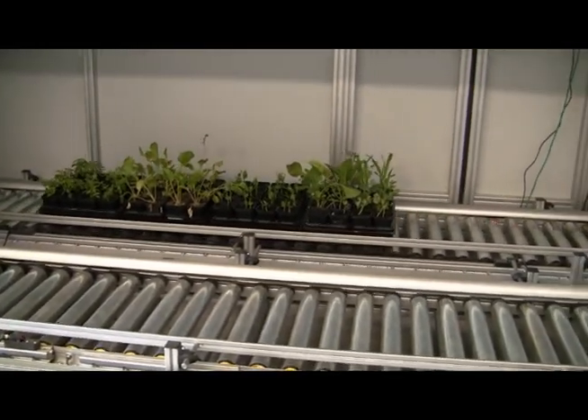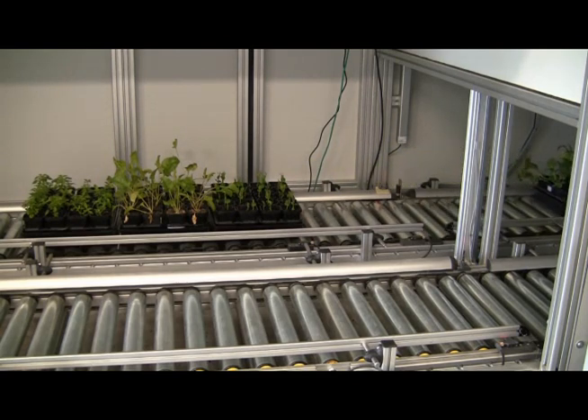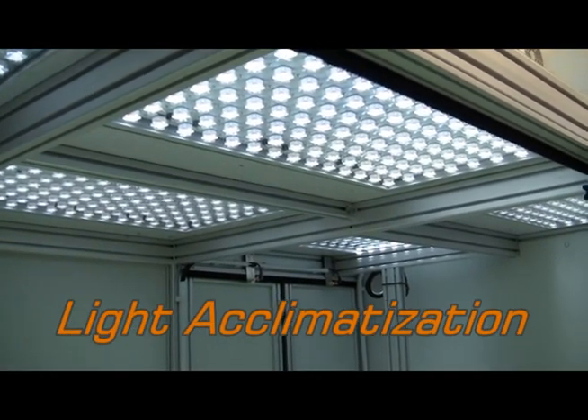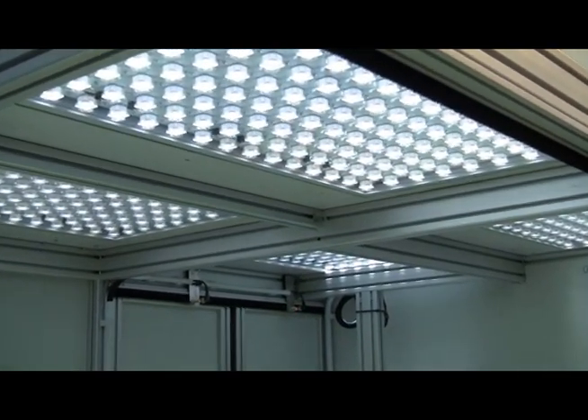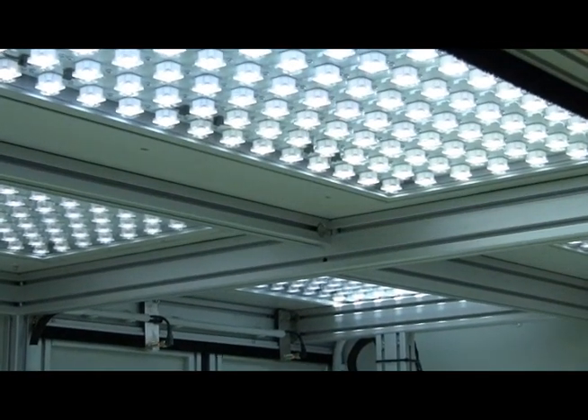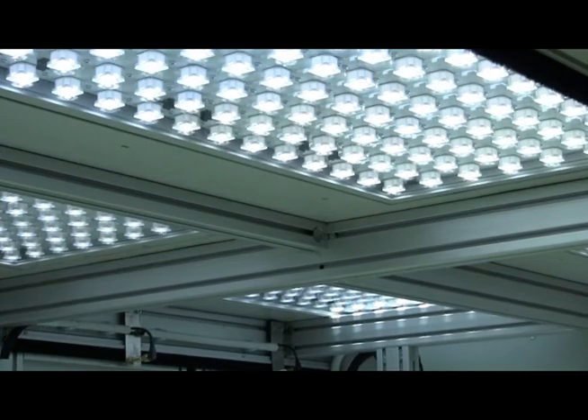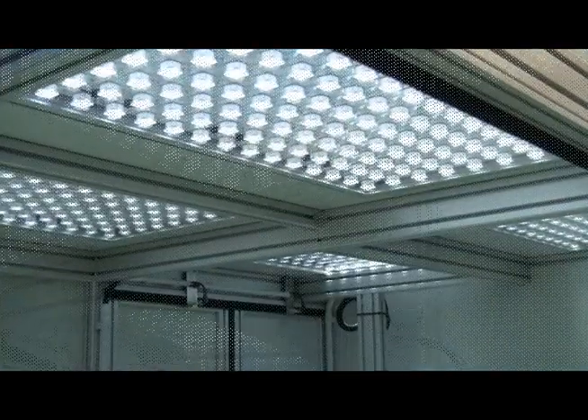The PlantScan conveyor has a rugged design and is adjustable to accommodate both plants in trays and plants in individual pots. Lateral barriers may be adjusted to change the effective width of the conveyor to accommodate pots of different sizes. A key feature of the PlantScan is its overhead banks of LED panels. The PlantScan is divided so that its long axis is in two sections, each with independent LED lighting. Plants in one half may be dark adapted prior to chlorophyll fluorescence imaging, whereas plants in the other half may be pre-equilibrated at a user-defined actinic irradiance for light adapted fluorescence measurements. High output, cool white LEDs are most commonly used for equilibration, but users may choose to populate the LED panels with wavelengths of their choice. Irradiance levels are controlled in software and lighting protocols may be pre-set. Unlike other light sources, the LED light panels have very little heating effect on the plant.